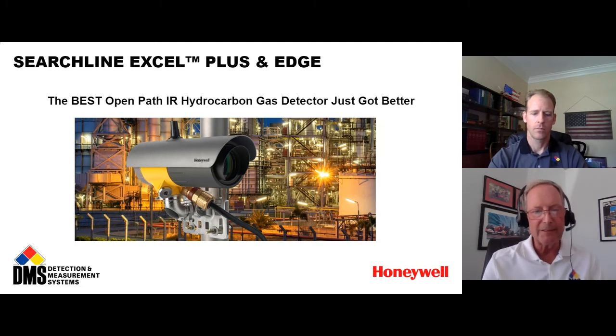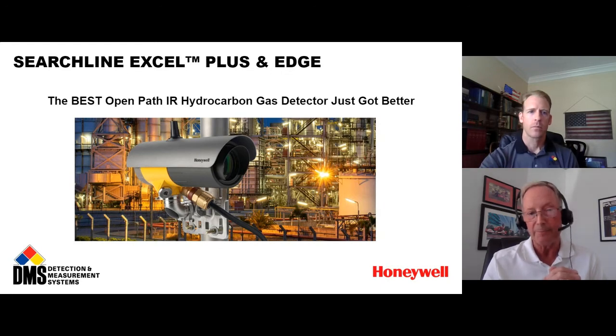And so you have essentially a continuous infrared beam extending hundreds of feet, where the gas can cross at any point, and you have detection. So it provides an advantage from a coverage standpoint that's really unmatched, certainly by point detectors. And the next slide I have is why open path hydrocarbon detection.